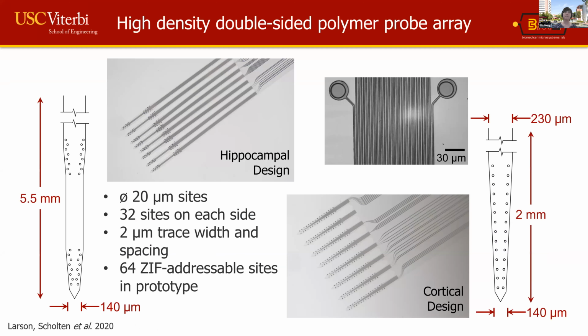All right, so very briefly, I'm just going to show you some of our more recent results of devices that we fabricated and are in the process of testing. So these are our newer devices. We have both a hippocampal design and a cortical design. As I mentioned earlier, the major difference here is that we now have electrodes on both the front and back side, so 32 sites on each side. And so if you have 8 of these, there are 512 electrodes on each one of these arrays.